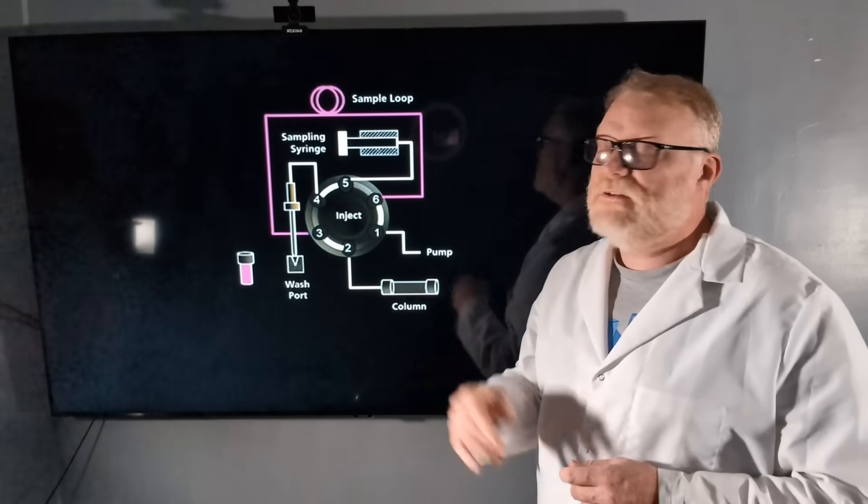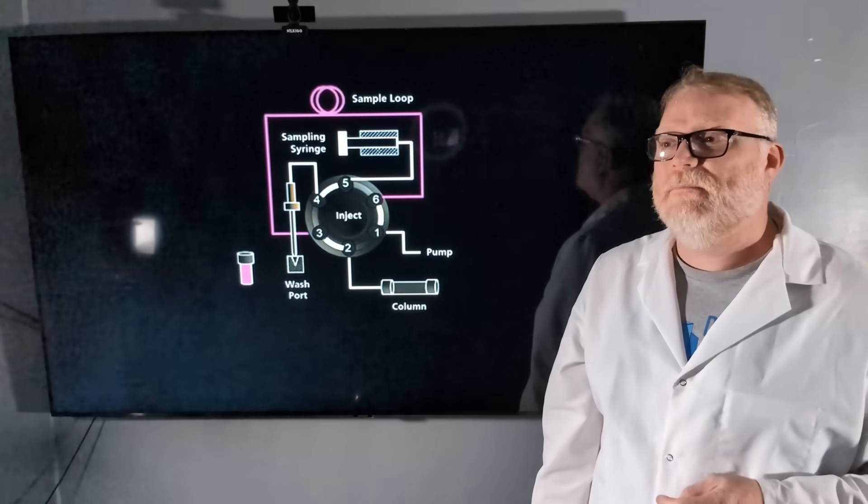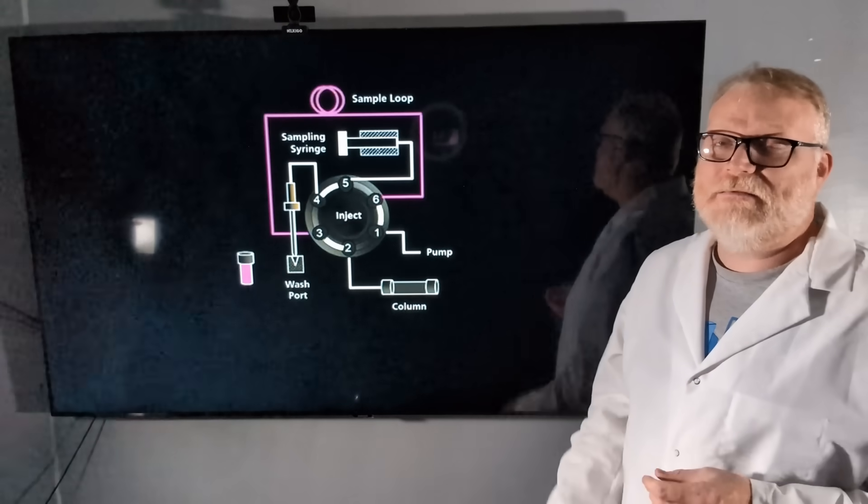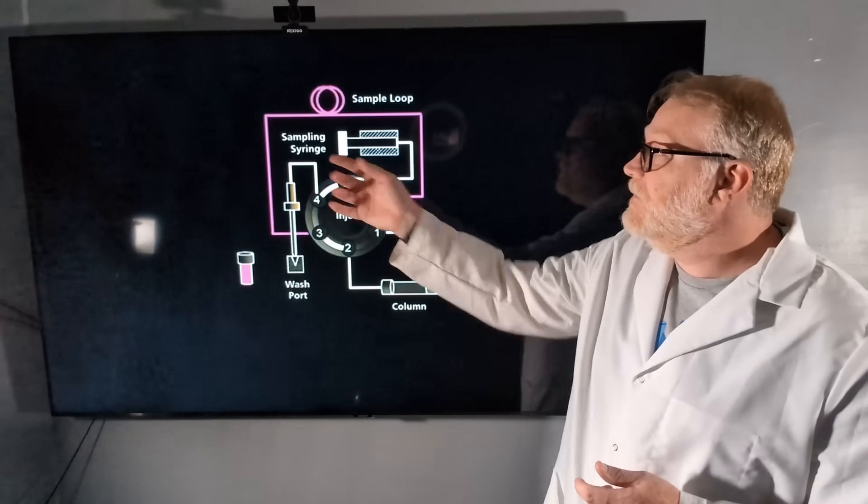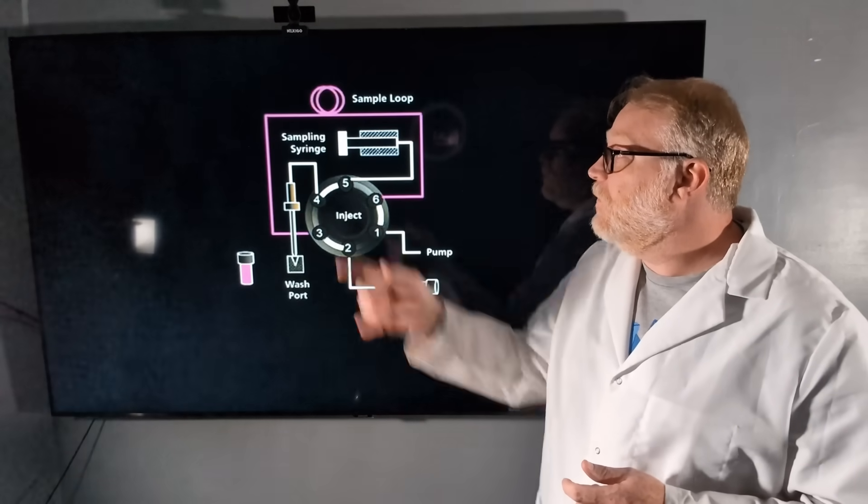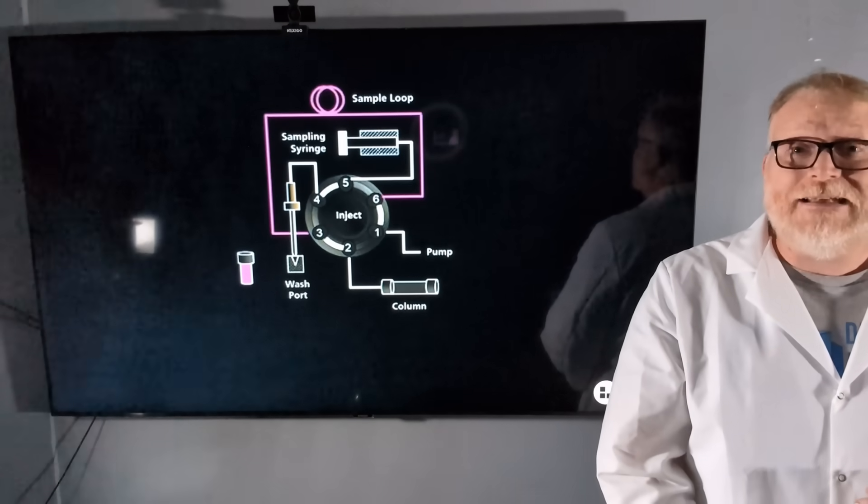The needle then moves to a wash port or a wash vial, depending on what type of manufacturer has installed. And then the sampling syringe is going to be used to wash out that sample needle.